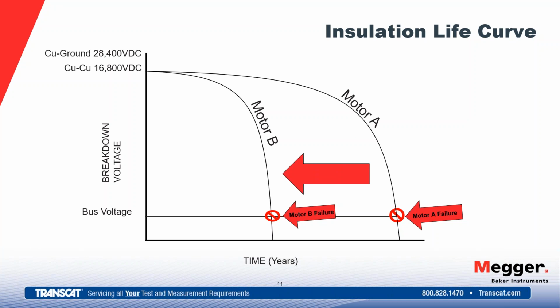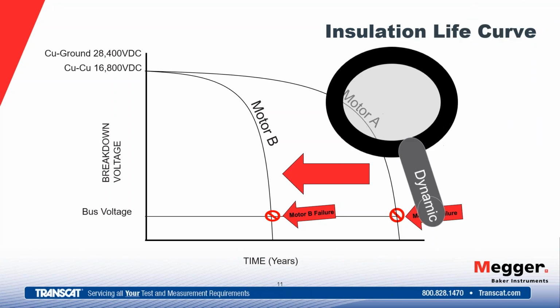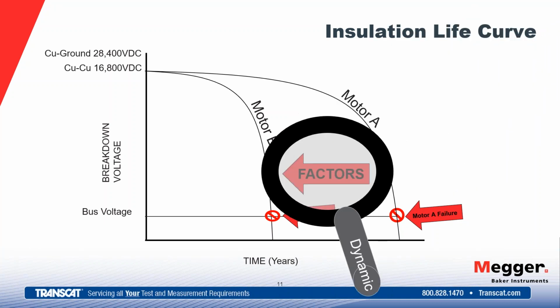And so to identify those factors as to why that motor is being on a shortened path, that's where our dynamic testing comes into play. It will reveal those factors. So again, the static testing, being insulation resistance testing, phase-to-phase resistance, and the surge test, DC high pot, all those help directly evaluate that insulation. It tells us where on this curve it is. Dynamic testing is going to identify factors that are causing that motor to be on a shortened path.